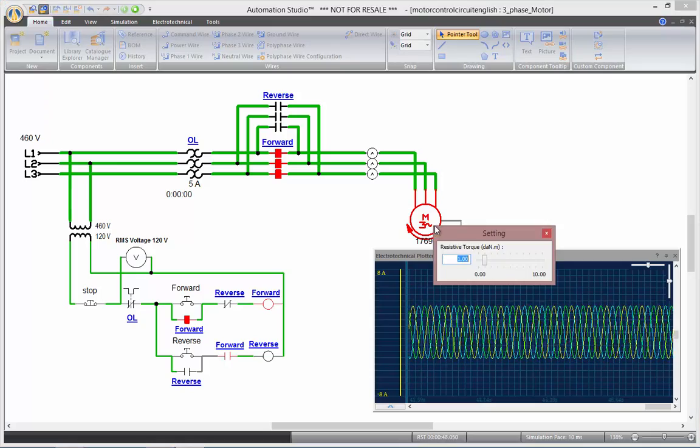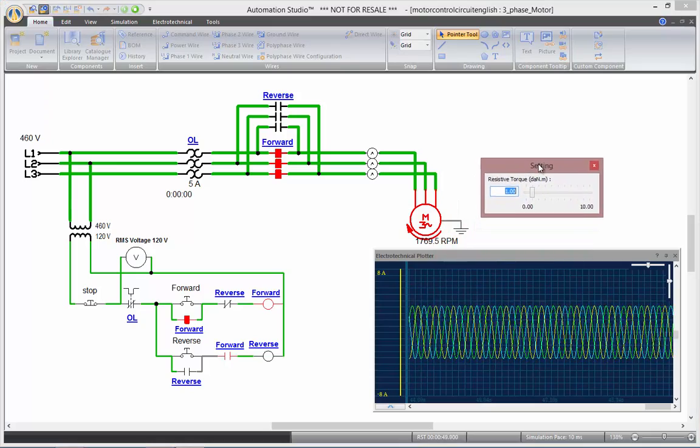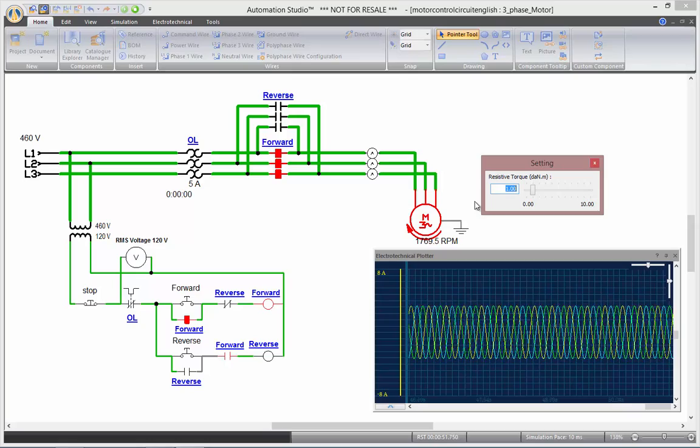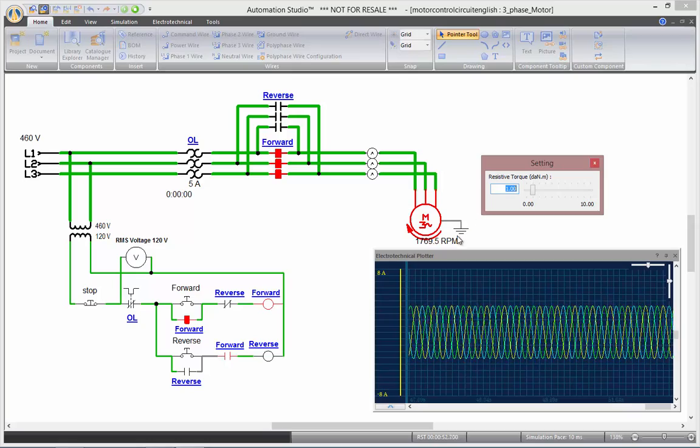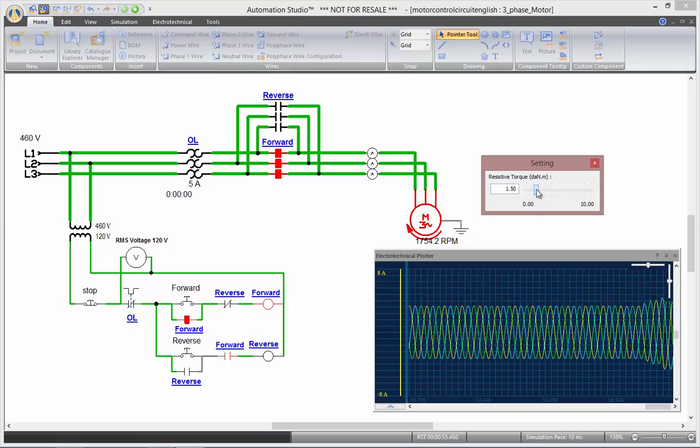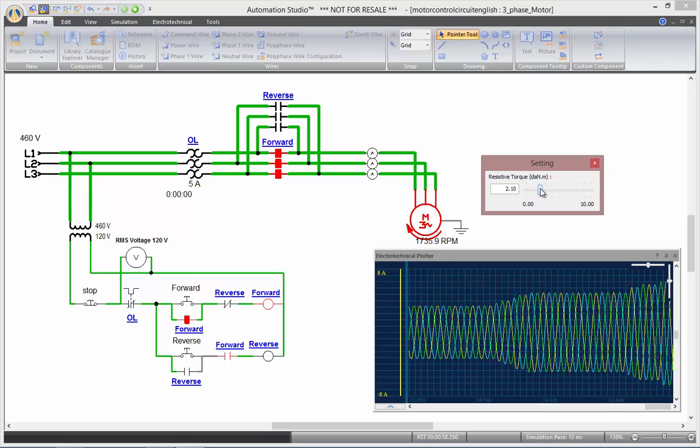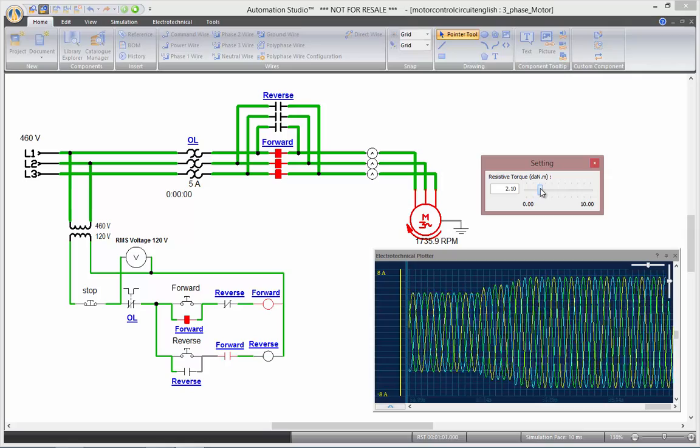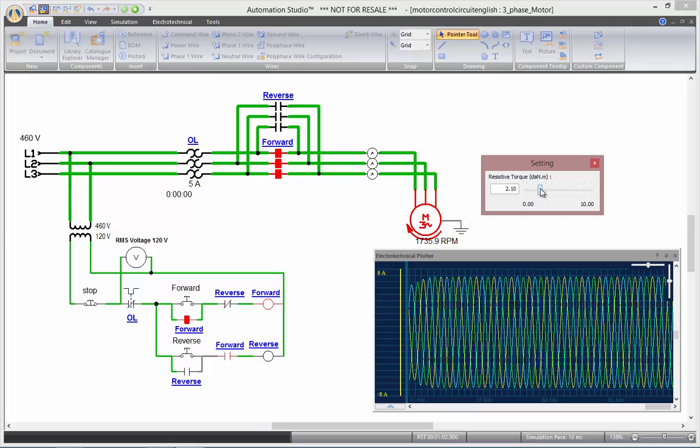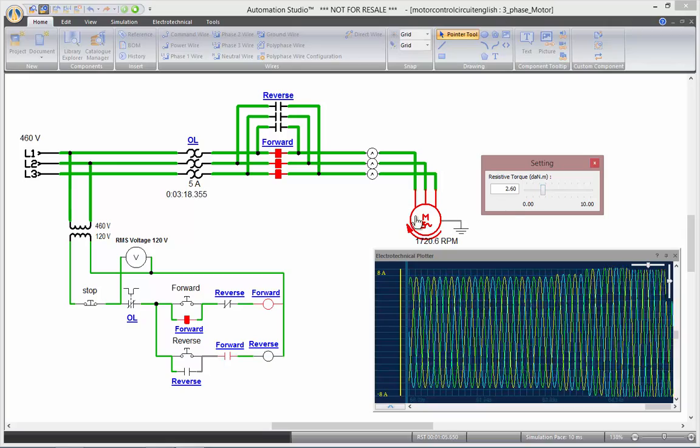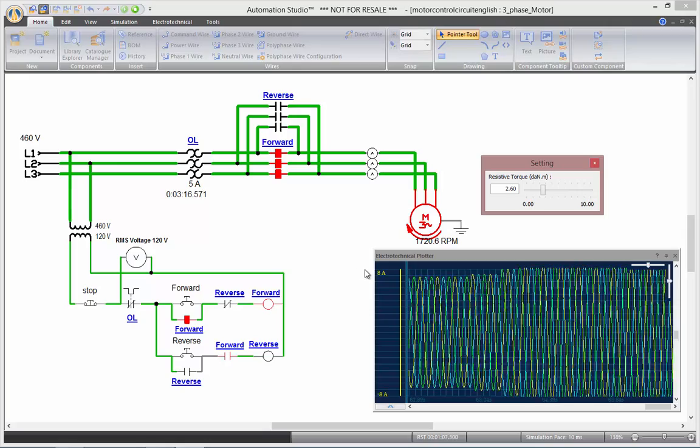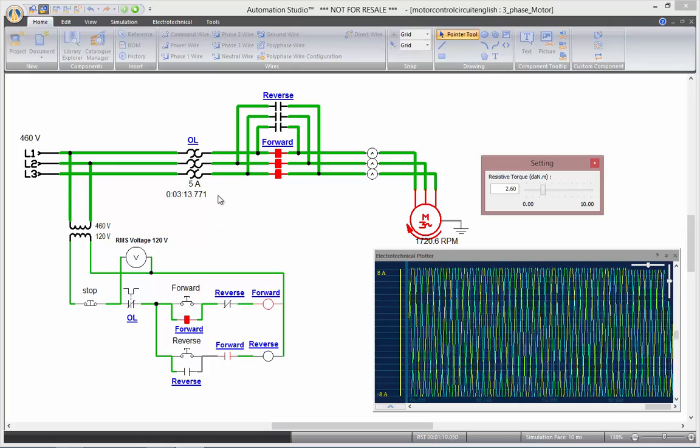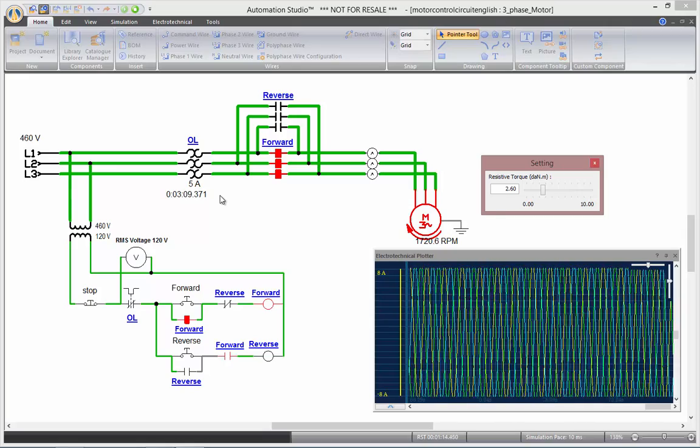And as I increase my resistive torque, you'll see the current consumption increase and the speed decreasing. So the more I increase the torque, the lower the speed, the higher the current consumption. And as I go over 5 amps, you see there my overload protection countdown starting to run.